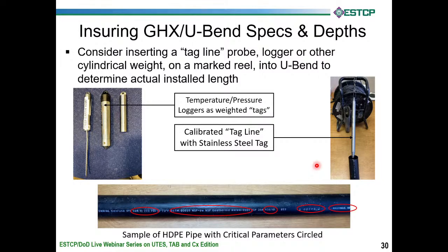One way you can kind of avoid that is on this piece of pipe down here. I know these numbers are hard to read, but one of the things stated on the side of the pipe is often the length of the pipe. If it's a big roll of pipe you're using for headering, it doesn't matter. But for U-bends, you can have the length printed on the U-bend, typically, what is it, Brandon, every 2 or 3 feet or so. And unless the contractor gets really creative and hacks out a section of the U-bend before he puts it down the hole, you can read the length of the pipe off the pigtails sticking out of the ground and know what length it is. And we think that's an important parameter.